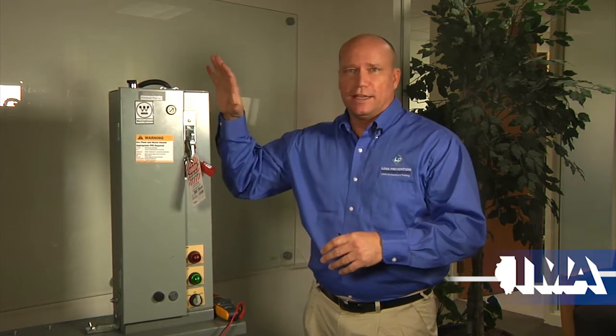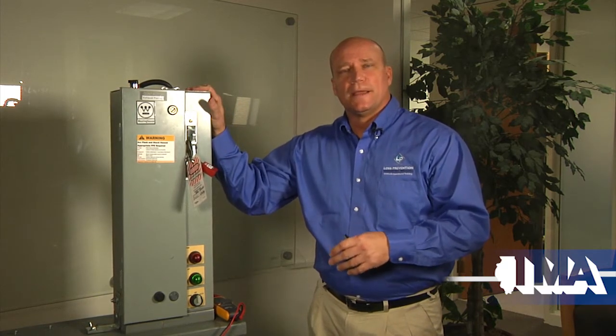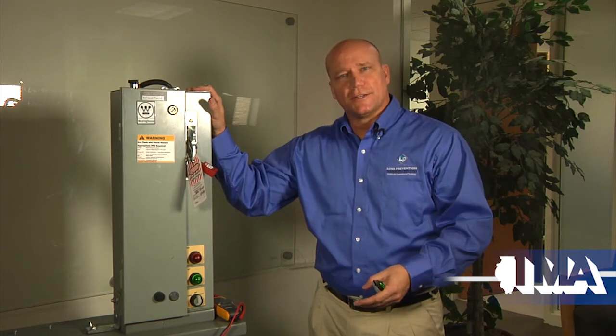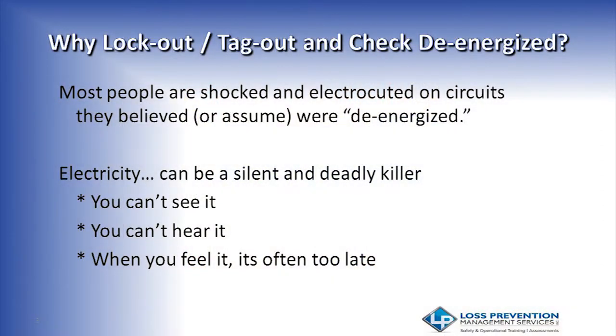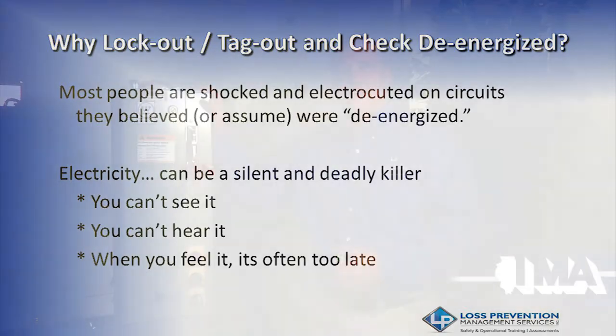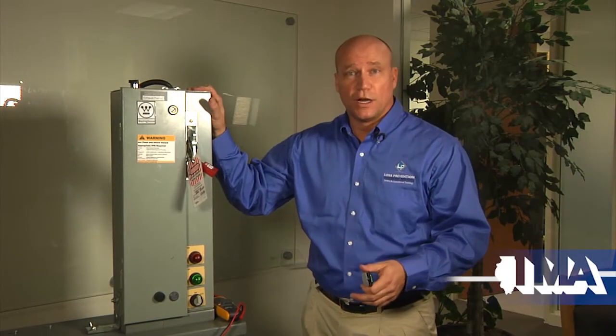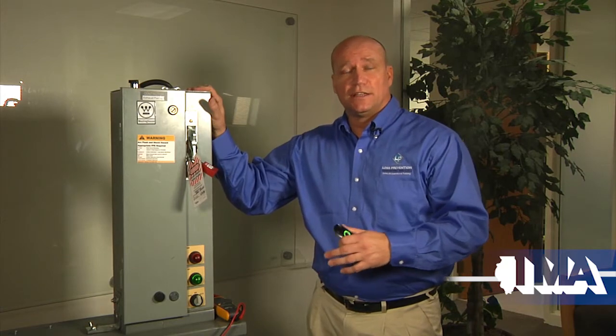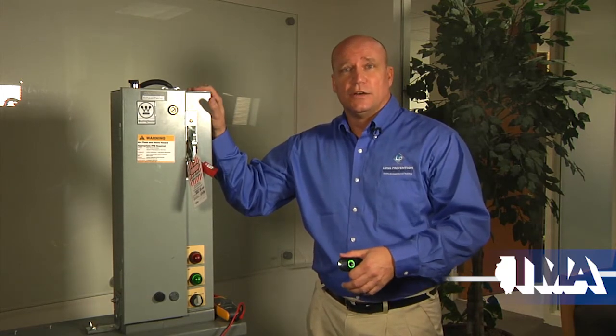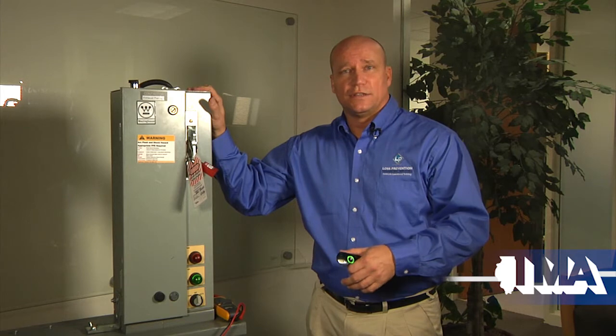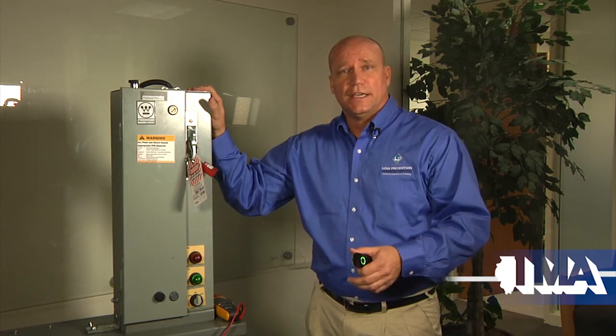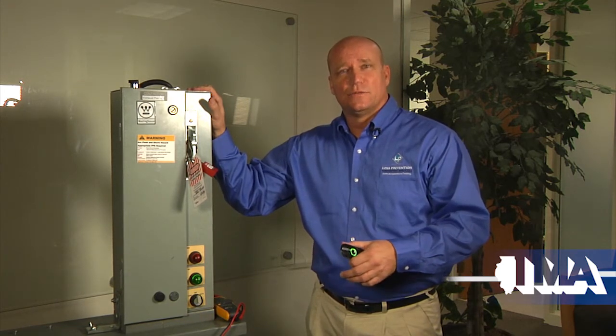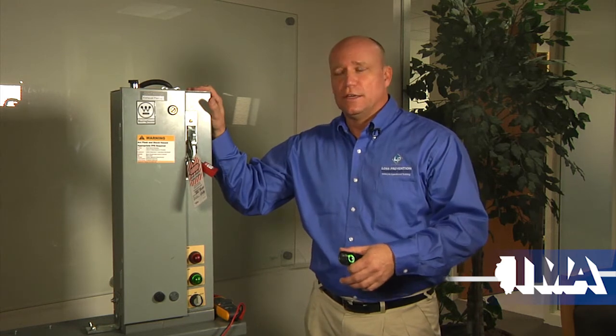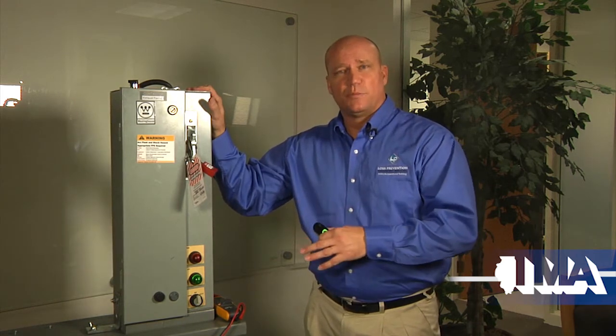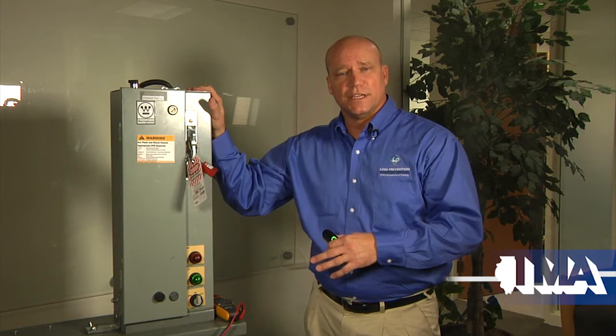During switching and during a live dead live process as well, there's always a possibility of an arc flash. So there are things that you need to do to protect yourself. One thing that we like to train is not only why you're doing it, but why it's a requirement. In this case, doing a live dead live is a requirement of OSHA. OSHA lockout tagout is Article 147 of General Industry, and it's also subpart S, which is Article 333, which talks about the live dead live process and verifying electrical equipment is de-energized.